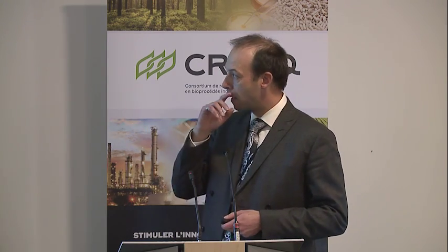Do we need some physical separation between all the sectors, and also with the HVAC of the building? It's very important because if we don't have any separation with the HVAC, it will be possible to get dirty air into the clean section, and it will be possible to have contamination of the site where you want to produce your product. So here we can find an example of a plant where we produce some proteins for the drug industry.